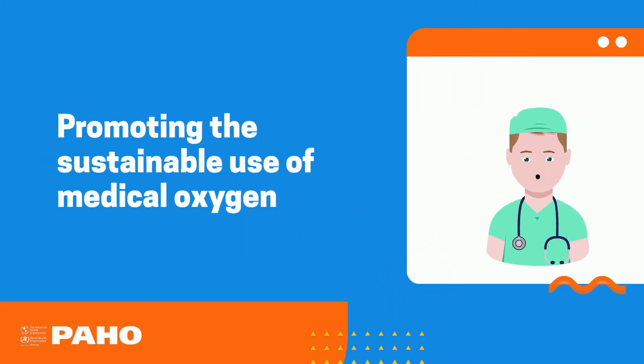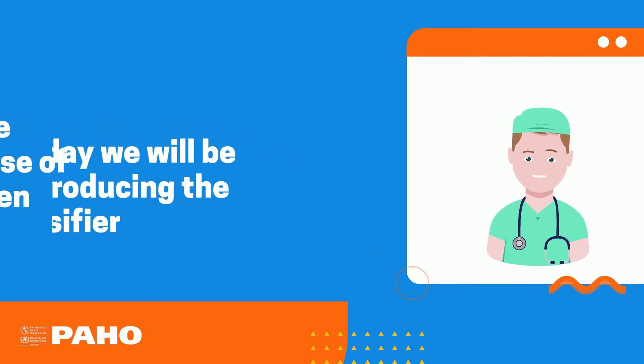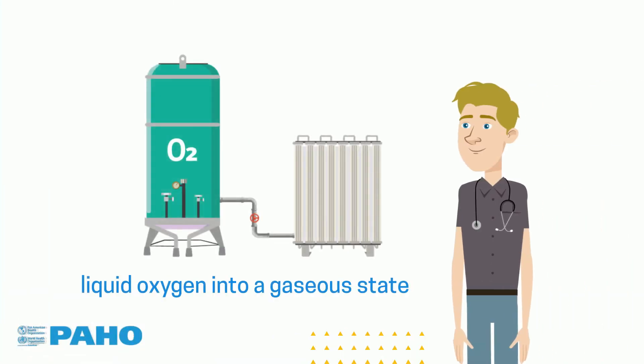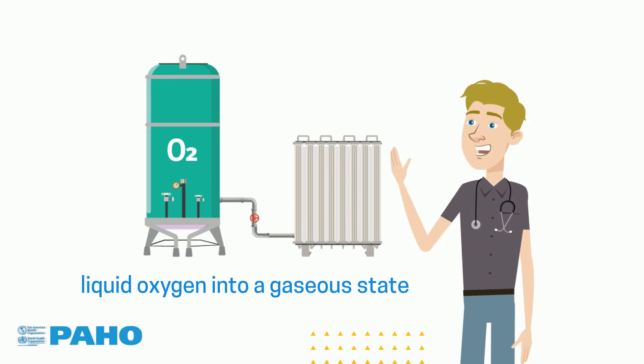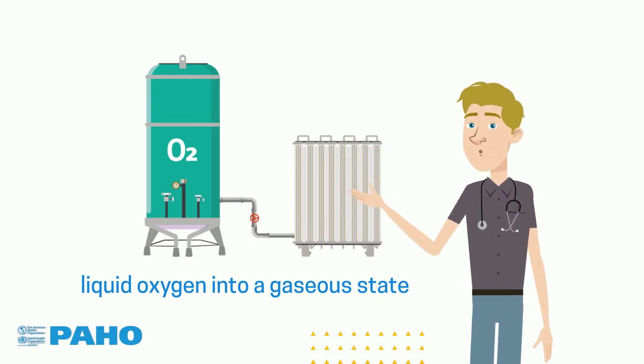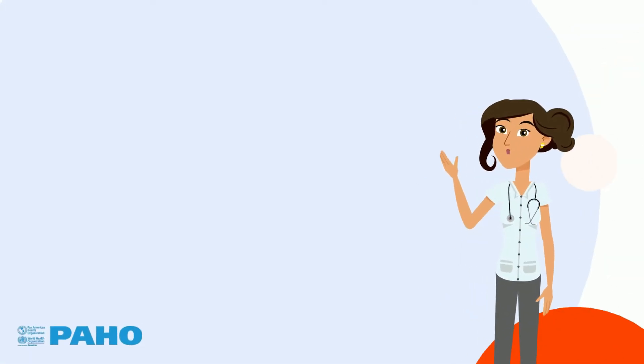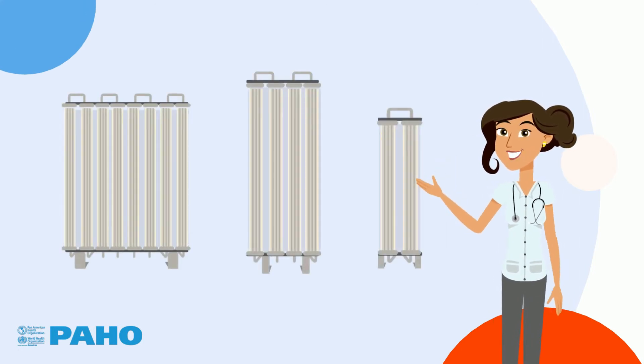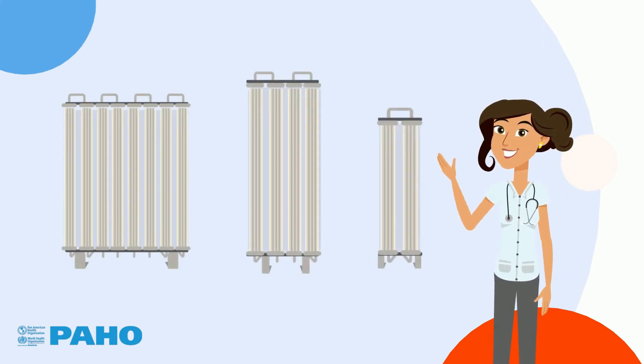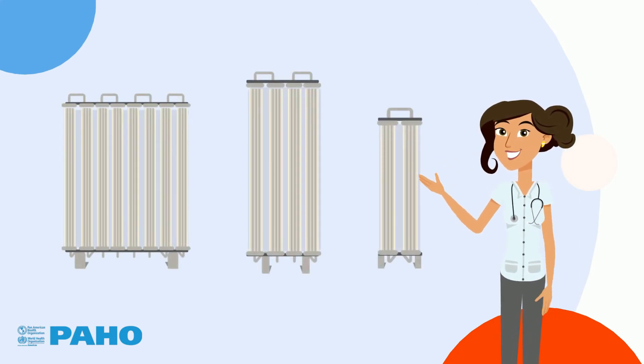This video is part of the series promoting the sustainable use of medical oxygen. Today we will be introducing the gasifier. The gasifier is a component that transforms liquid oxygen into a gaseous state. Gasifiers exist in sizes that vary according to the amount of oxygen that needs to be evaporated for hospital use.